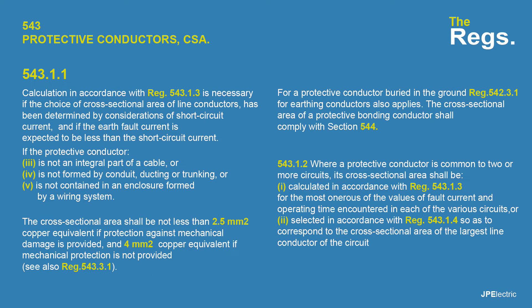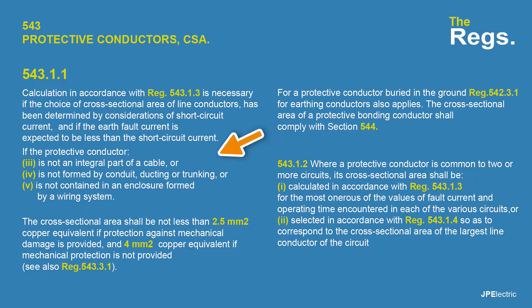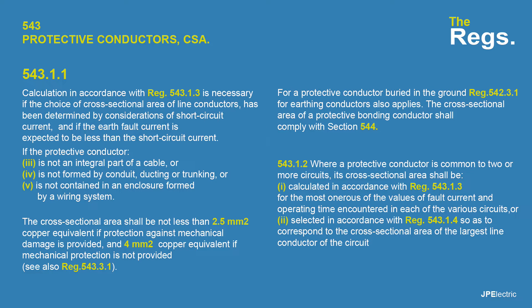The regs then go on to tell us when calculation is necessary, giving examples: if the protective conductor is not an integral part of a cable, it's not formed by a conduit, ducting or trunking, and it's not contained in an enclosure formed by a wiring system. It also tells us the minimum cross-sectional area in those circumstances, and what to do when a protective conductor is common to two or more circuits.